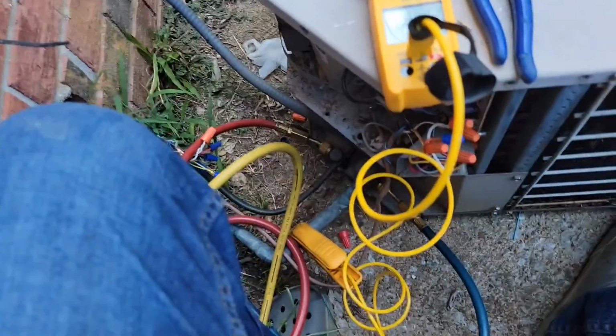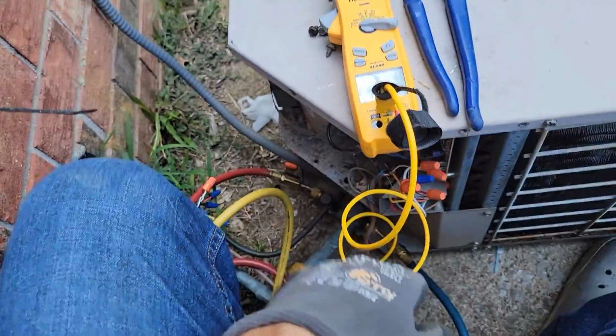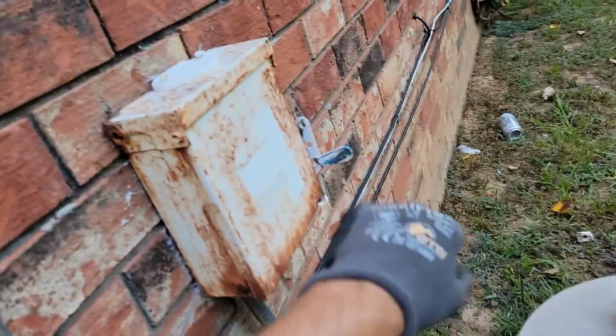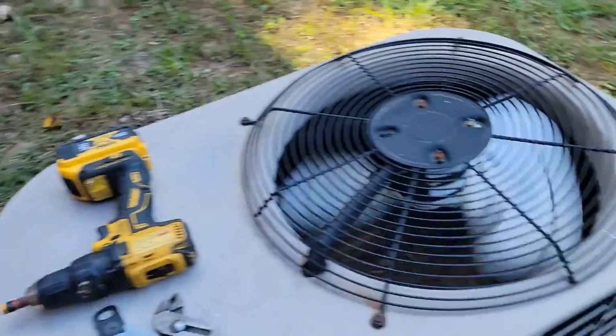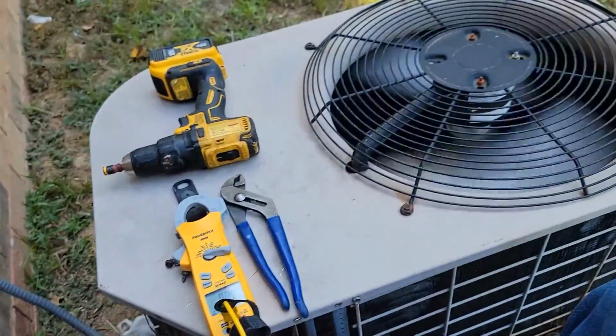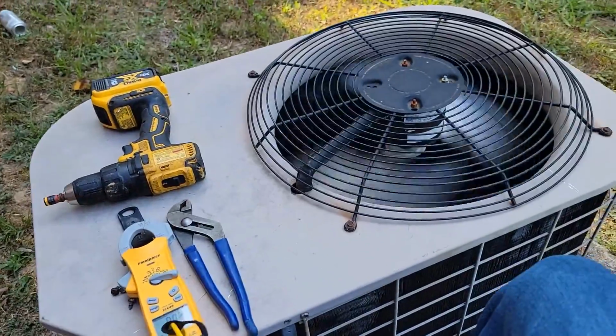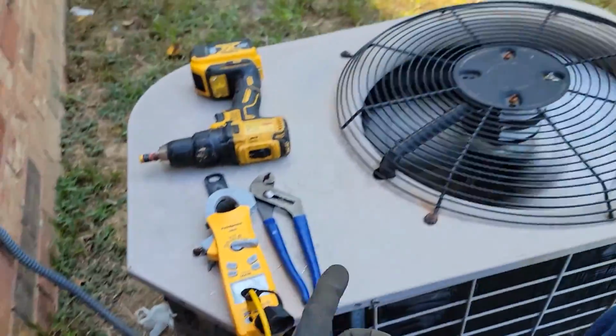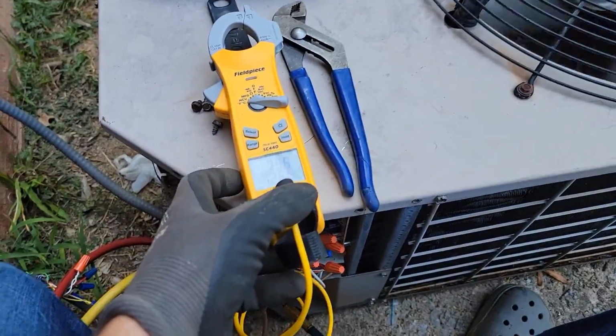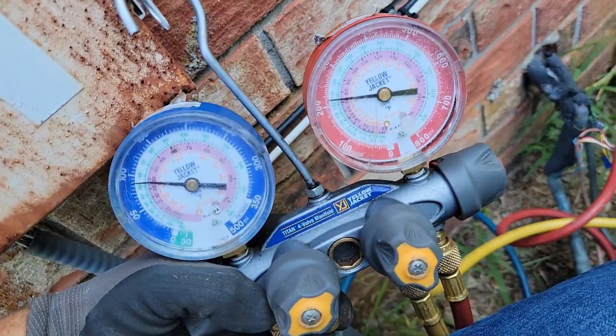Some technicians would order a new reversing valve coil. They would say, this one's not the right one, but that's the one that they sent. So I made it work. Make it work. Gauge is hooked up, got my temperature clamp on my vapor line. Beautiful. I love it when it works. So reversing valve should energize in the cooling operation. So we've got 24 volts to that coil. I'm gonna check the pressures and we're gonna be in good shape.